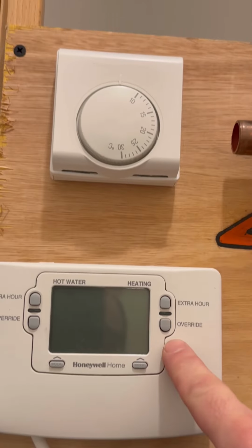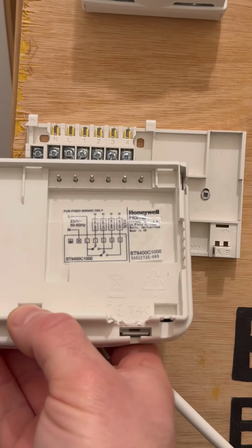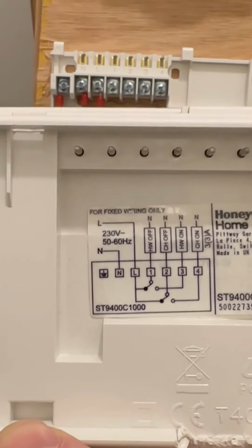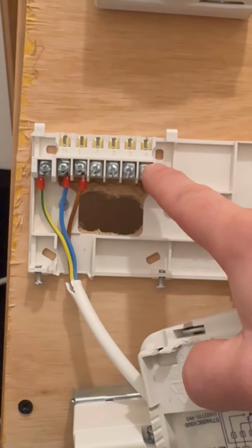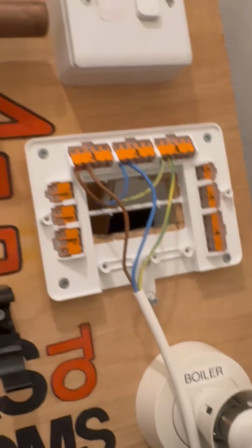So we're going to do heating first, we're going to go to the room stat. So from here to the room stat. Back of there, heating on, can't really see it that well, essentially heating on number 4. So we're going to take number 4, we're going to go to here, up to the room stat, through the room stat back, then to the white, then to the orange, fire the boiler.